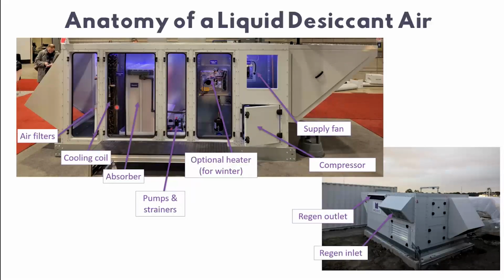So coming off that coil saturated, as I suggested before, we're then passing our saturated air through our humidity absorber, which is a static media within the airstream, so no cross-contamination between the two airstreams, no carryover of heat between the two airstreams. And this media is being pumped, gravity-fed, impregnation-style falling film of concentrated desiccant, which runs down these channels, condensing moisture out of the air into the desiccant, trapping it. We have a pair of fractional horsepower pumps circulating desiccant through this media as well as to the other side of the unit to remove that moisture from the desiccant so the process can be repeated.